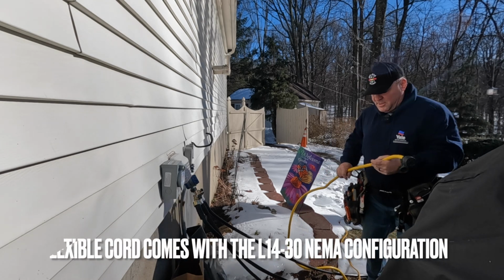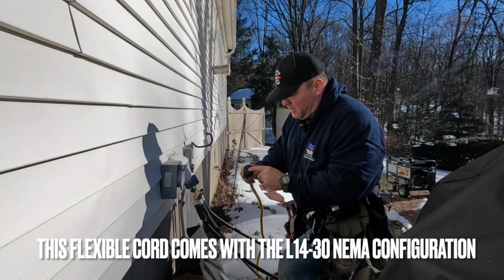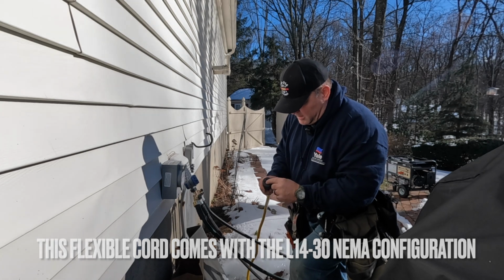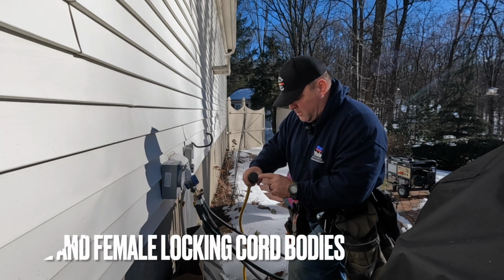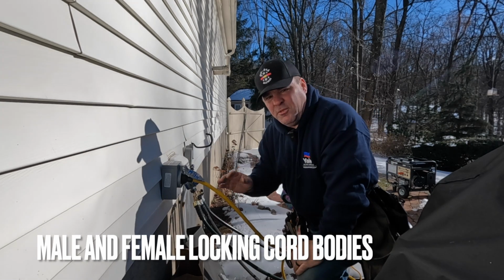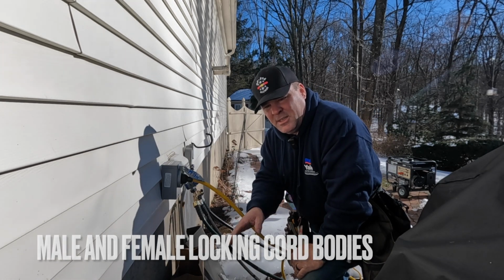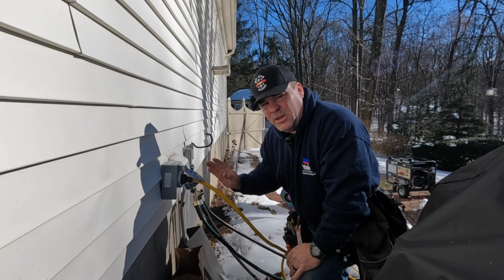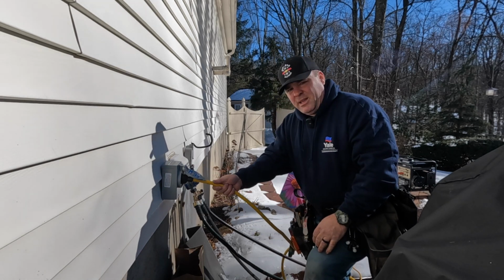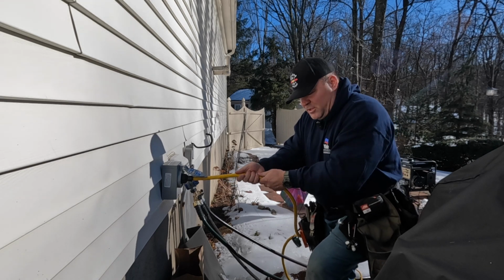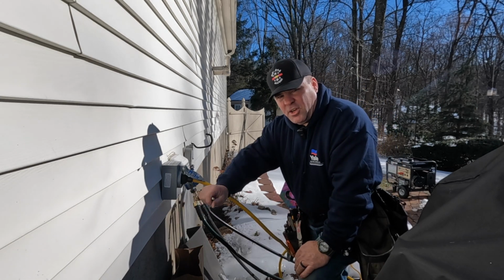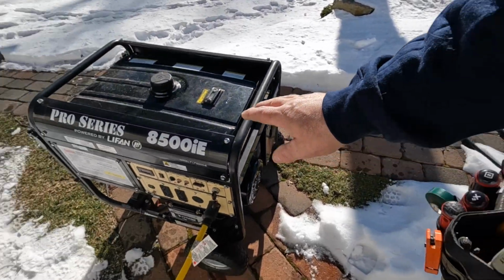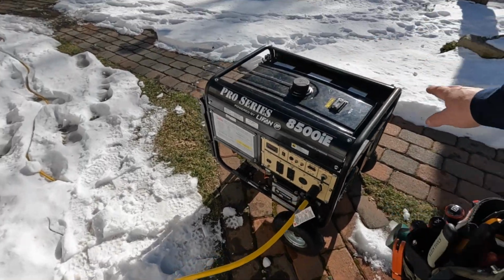All right, once the generator is on, you got a locking configuration here. The one that's looking like the L right here, or the backwards L, that's your ground. Let the voltage of the generator stabilize before you make your connections. Very, very important that you do that. Now that the female end is in, and as you see it locks, so you can tug on this, it's not going anywhere. You're gonna put it in and turn clockwise and it'll lock in place. The idea is that by the time you go back downstairs to make the changeover, the generator has been running for a little while and it'll stabilize the voltage.